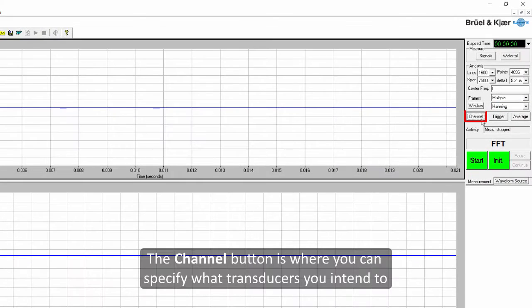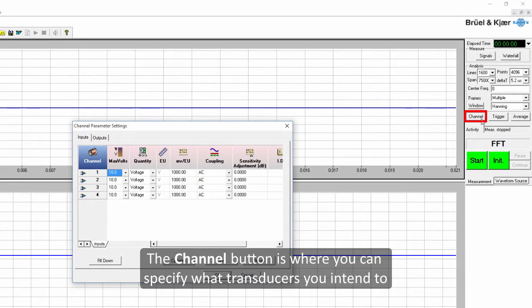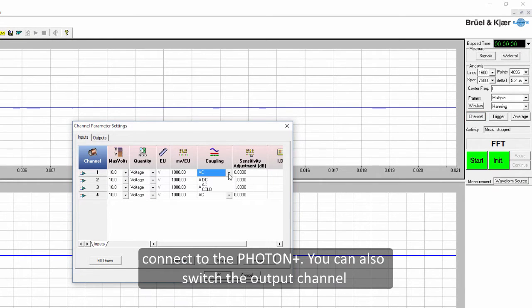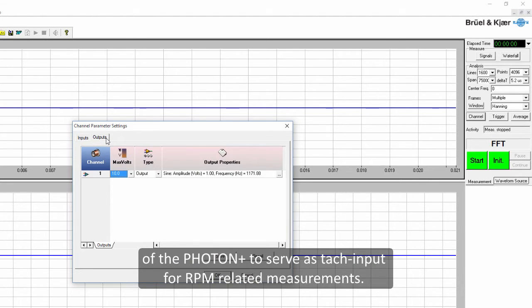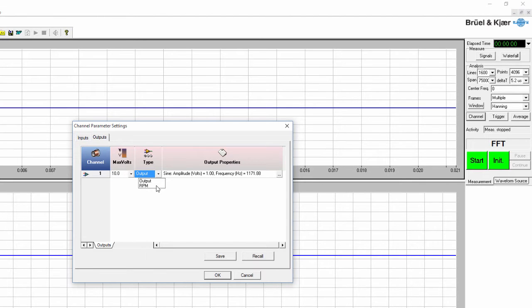The channel button is where you can specify what transducers you intend to connect to the Photon Plus. You can also switch the output channel of the Photon Plus to serve as tach-input for RPM related measurements.